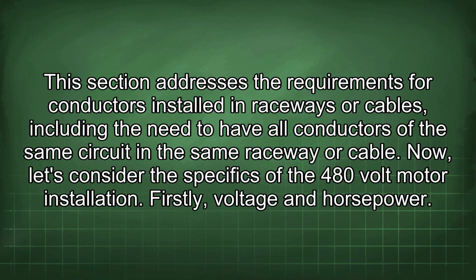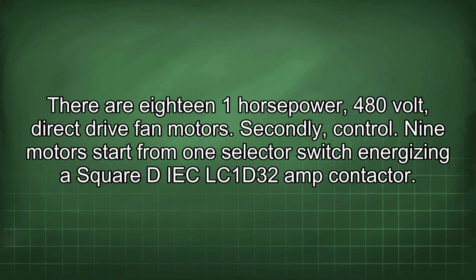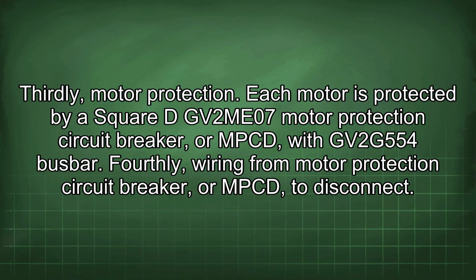Now, let's consider the specifics of the 480-volt motor installation. Firstly, voltage and horsepower. There are 18 1-horsepower, 480-volt direct drive fan motors. Secondly, control. 9 motors start from one selector switch energizing a Square D 32 amp contactor. Thirdly, motor protection. Each motor is protected by a Square D GV2ME07 motor protection circuit breaker, or MPCB, with GV2G554 busbar.